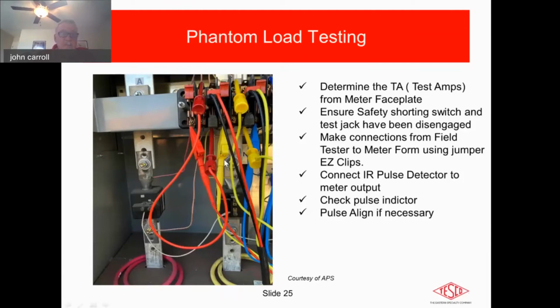So what we're doing is we're driving current into this duckbill. It then comes in the bottom here and comes around this cable and goes into the top. So we are bypassing the CT and we're going directly into the meter under a control condition, typically 2.5 amps.